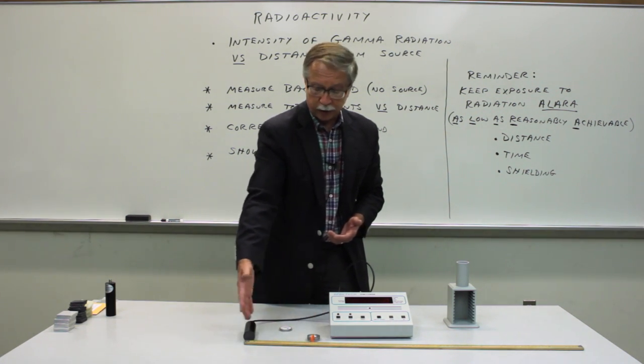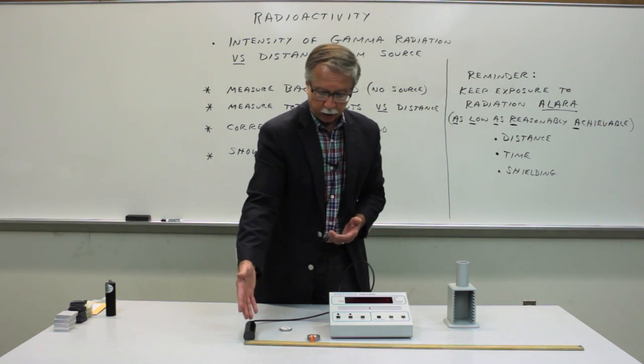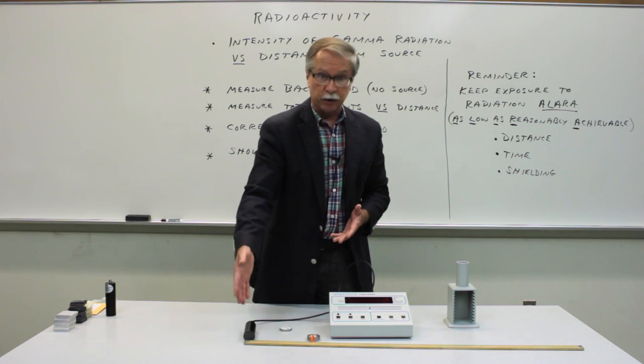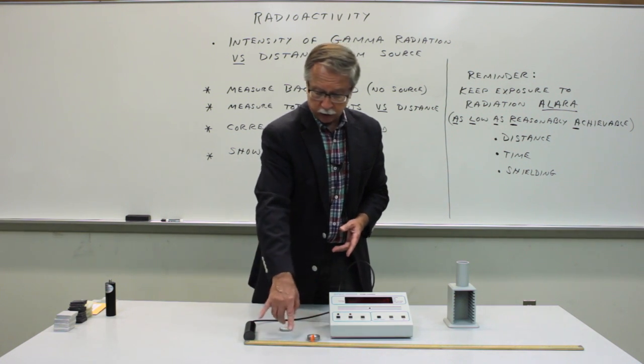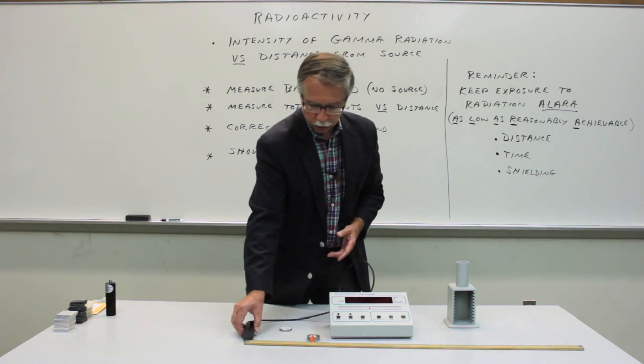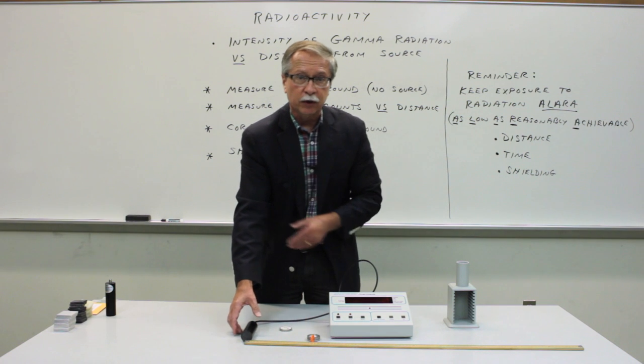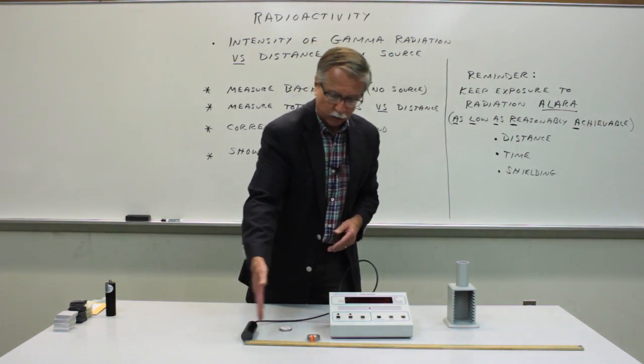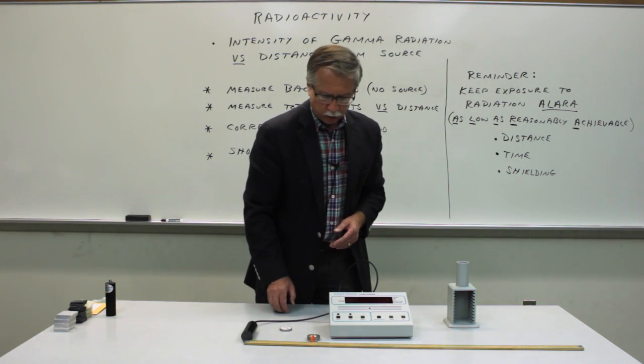That will ensure that you are counting only gamma radiation and not beta particles. The dependence on distance for beta radiation is very different and much more complex. So you want to filter out the beta particles, and an easy way of doing that is to have the side of the tube facing the source, ensuring that you are measuring from the axis of the tube to the center of the radioactive material.